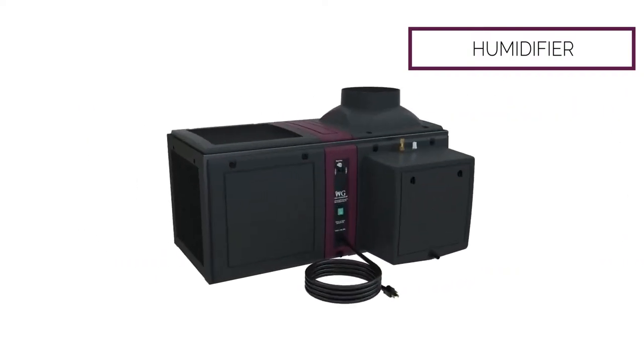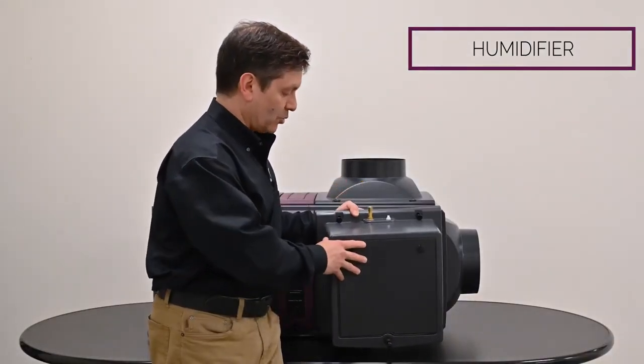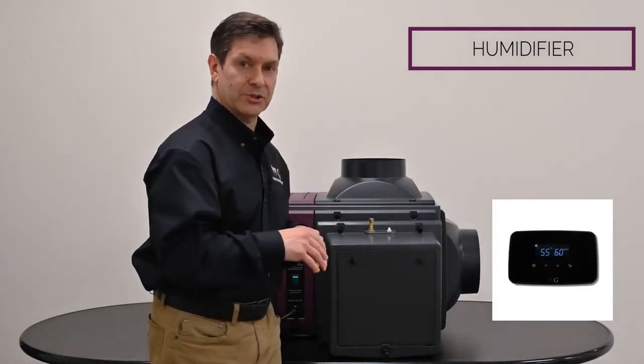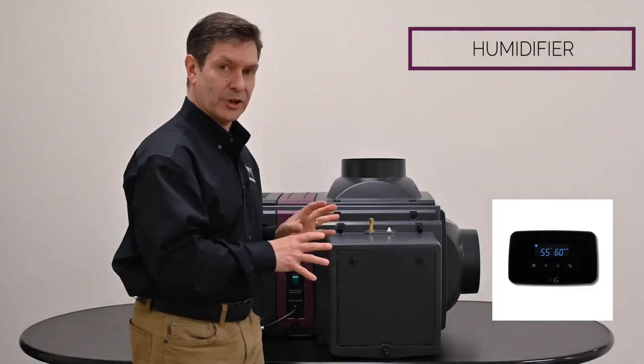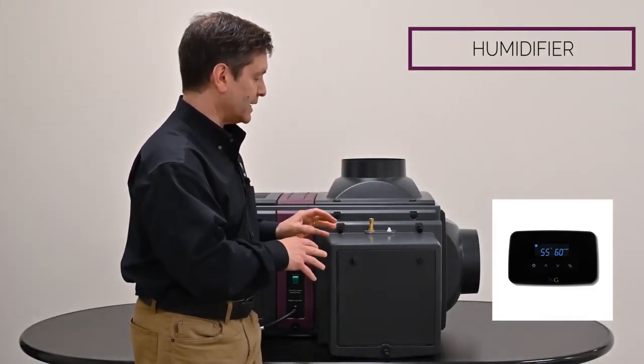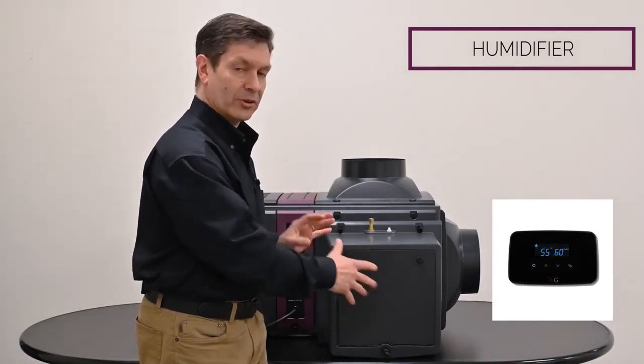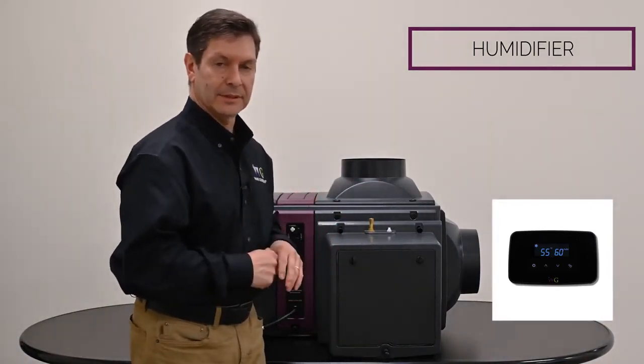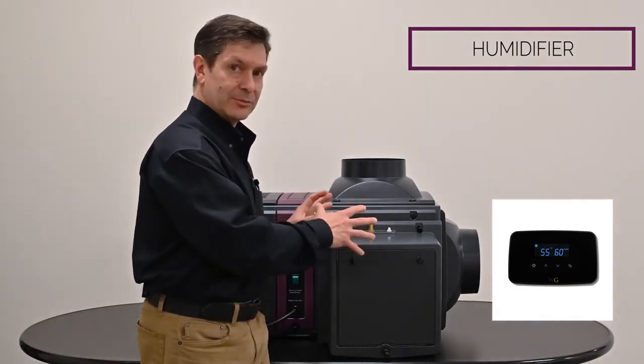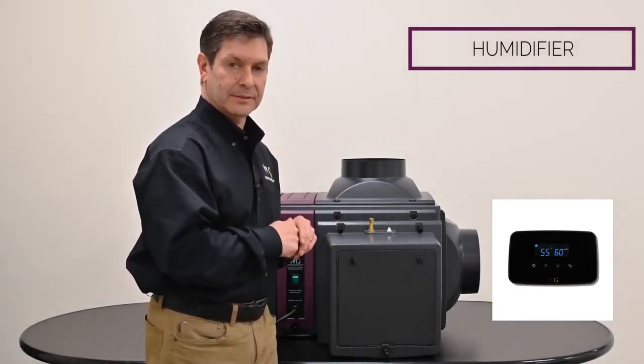The humidifier is connected to our Wine Guardian unit through a control cable connection at the top, as well as a connection at the side of the unit. There's a water inlet at the very top of the unit, as well as a water drain at the bottom. Everything is controlled through our main controller. Once there's a call for humidity, there's a solenoid valve inside the humidifier that opens up, allows water to drain over a wetted pad, and then out the drain. Once humidity is satisfied, that system shuts off and the humidifier turns off.